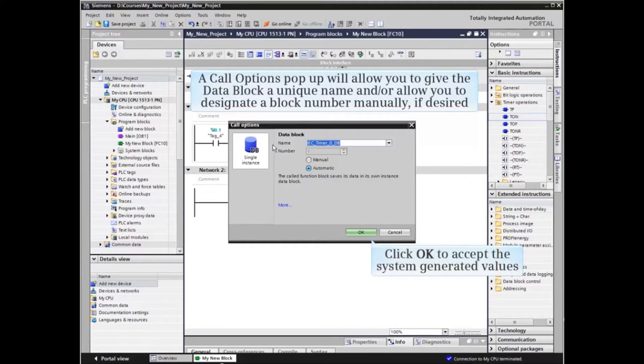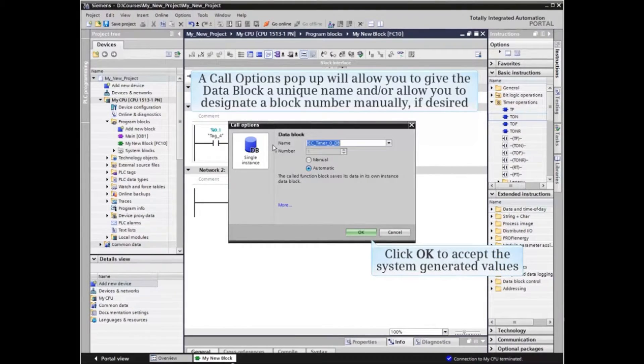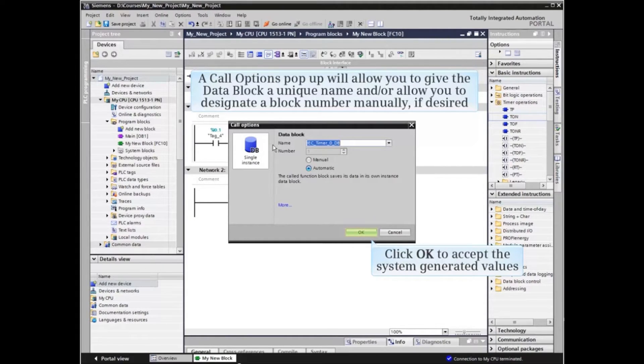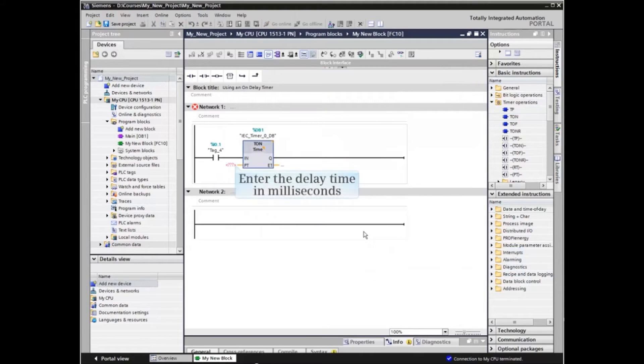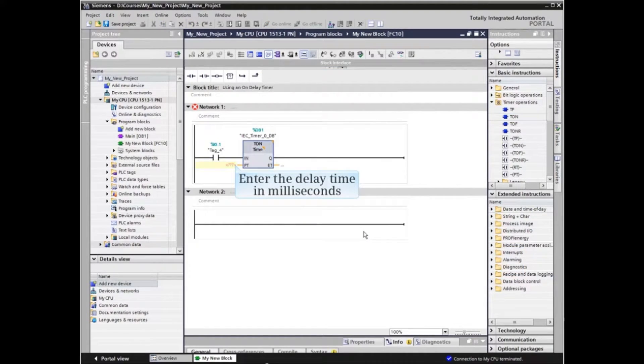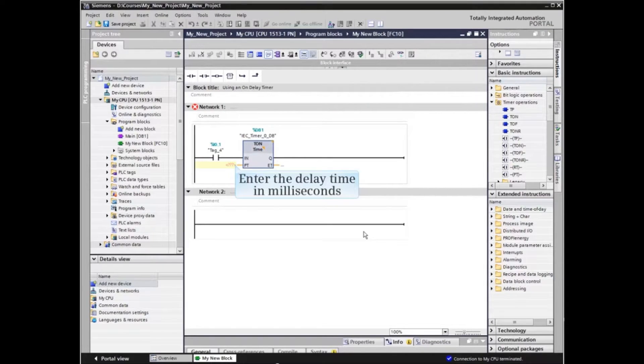The system generated name and block number can be accepted without change. In the example, we will accept the system generated values. At the PT input, enter the delay time desired, 5000 milliseconds in this example.